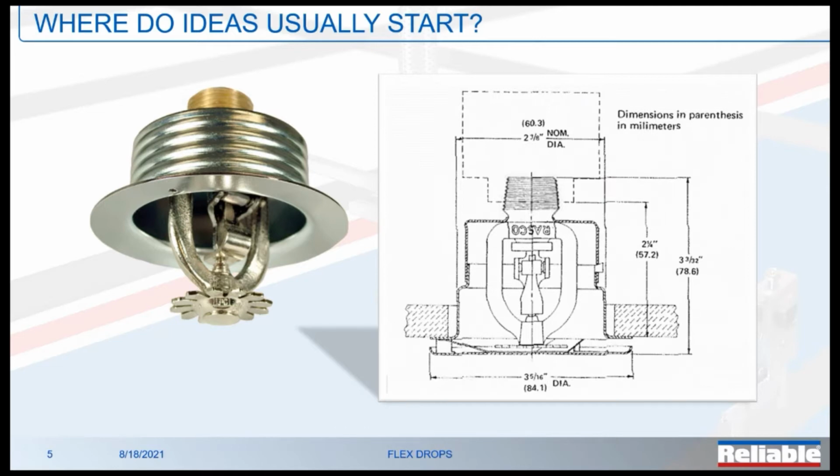It's what we had, and when we had concealed type sprinklers, when I came up in the industry, we cut drops as close as we could. We tried to make them fit. When they fit, it was great. When they didn't, the fitter did his job and he made those adjustments. But it was hard to pipe down to within an 1/8 of an inch. It was tough to do, right? It was really kind of a no-win situation.